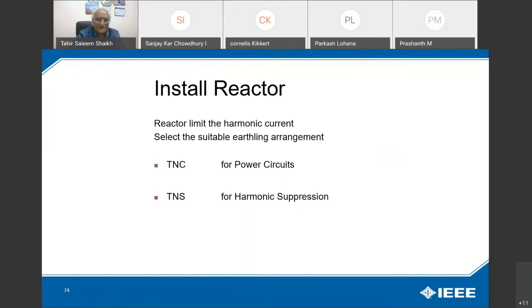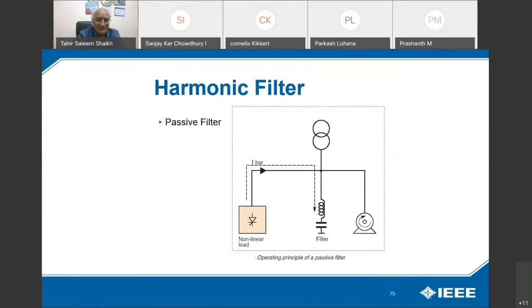So you should have a good grounding for the surge protector as well as for harmonic distortion limitations. If you install a filter, it is very expensive. You can see what filters are over here. This is a passive filter. The reactance and capacitance are connected to the nonlinear load, and this nonlinear load noise is filtered out through ground, and the pure sine wave goes to the linear load.